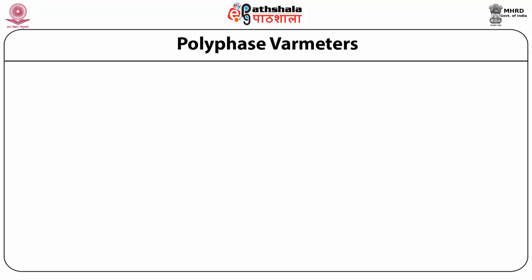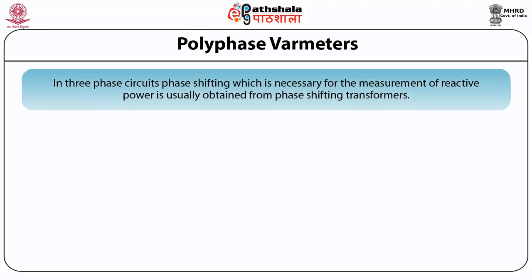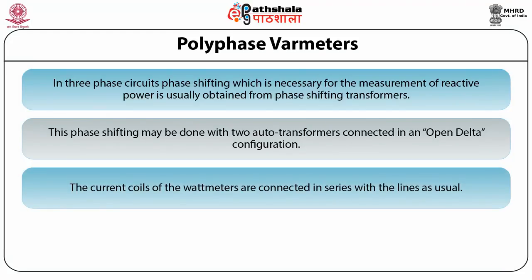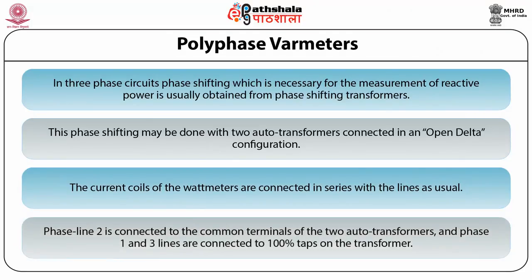Second is the polyphase varmeters. In three phase circuits, the phase shifting necessary for the measurement of reactive power is usually obtained by phase shifting transformers. This phase shifting may be done with two autotransformers connected in an open delta configuration. The current coils of the wattmeters are connected in series with the lines as usual, while phase line 2 is connected to the common terminals of the two autotransformers and phases 1 and 3 are connected to the 100% taps on the transformer.